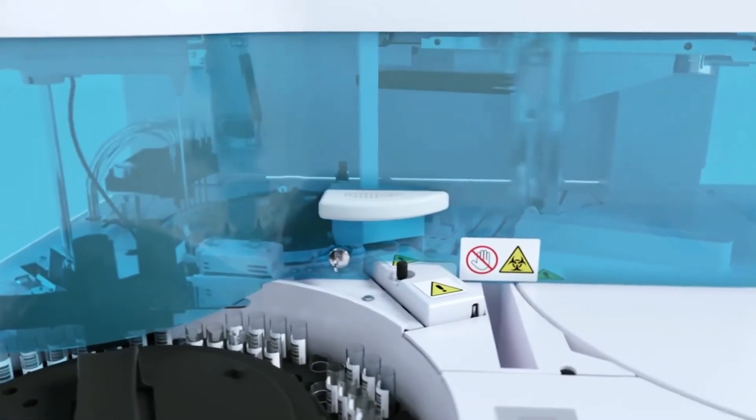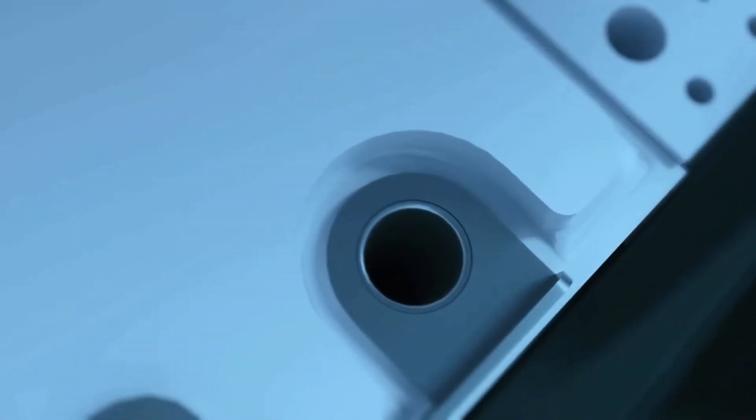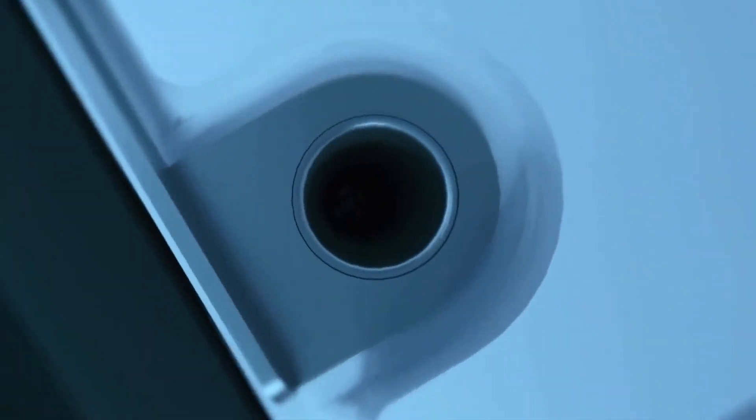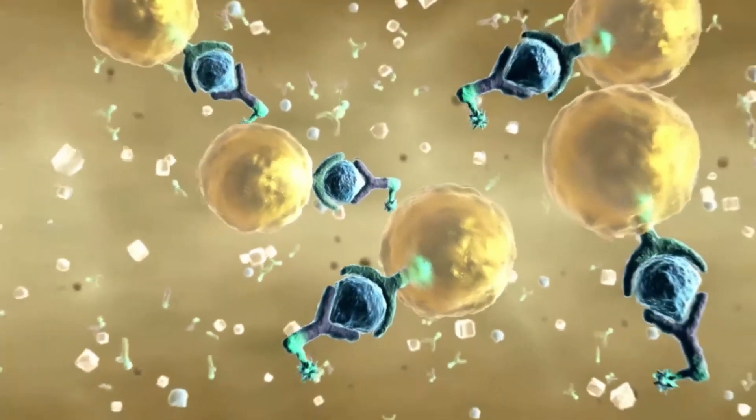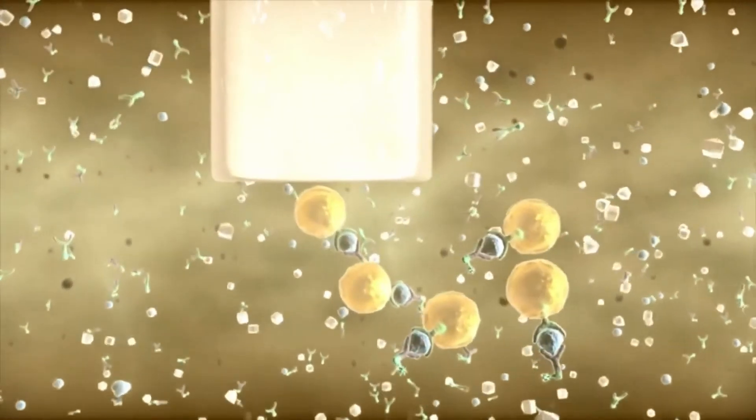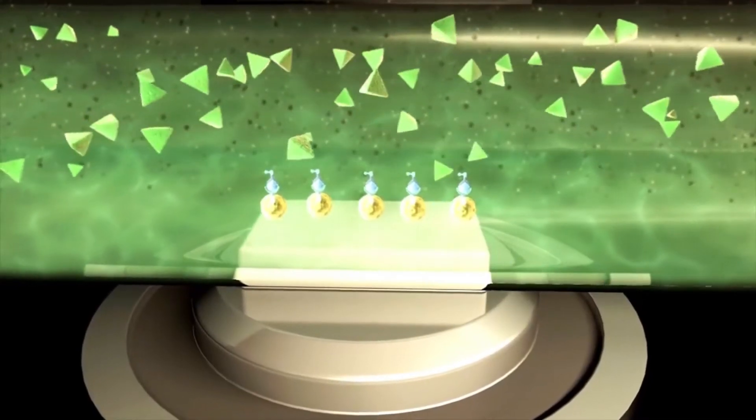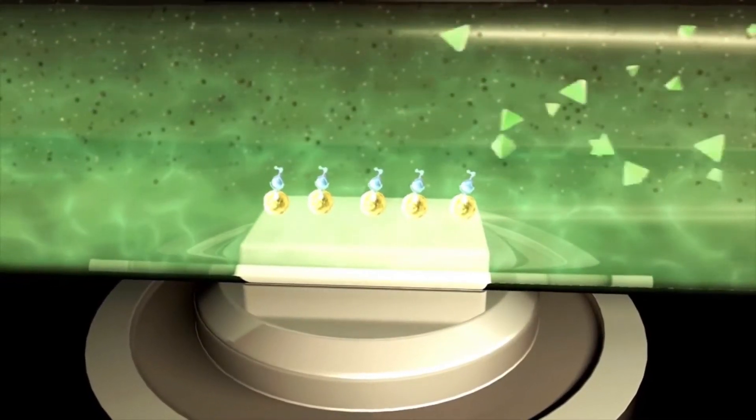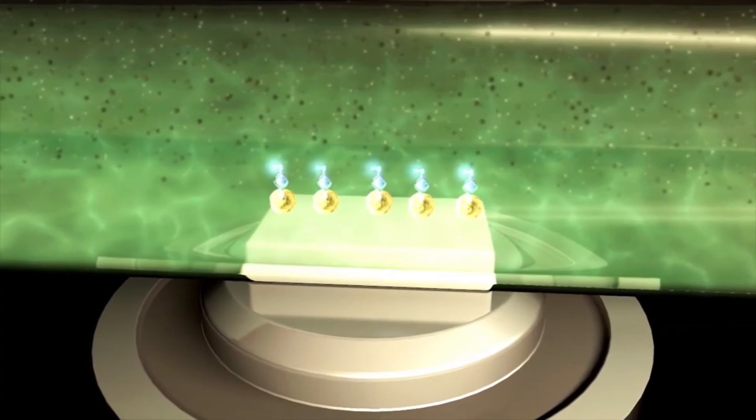The new mixture attained is carried out in either of the two areas, colorimeter or flow cell. If the mixture goes to the colorimeter, the absorbance can be measured there while it remains in the reaction vessel. In the case of flow cell, the mixture is sent to flow through the colorimeter to measure the absorbance. This way, the analyzer can calculate the relevant concentration.